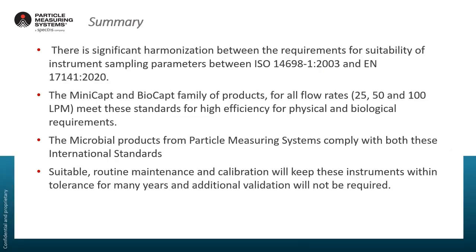In summary, there is a lot of harmonization between the requirements for ISO 14698 and EN 17141. The MiniCapt and BioCapt families of products we offer for all flow rates meet those standards and demonstrate high efficiency for physical and biological requirements. Microbial products from Particle Measuring Systems comply with both of these international standards, and with most instruments, routine maintenance and calibration will keep them within tolerance for many years — additional validation won't be required.